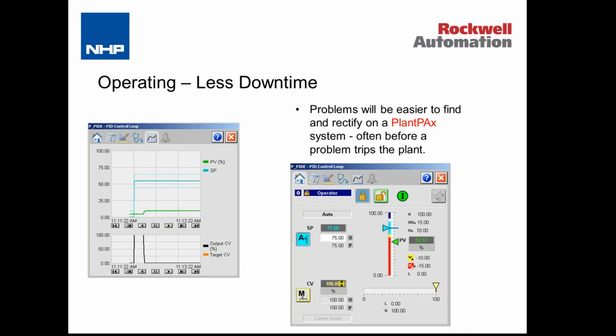Some of the things that you can see here on these faceplates, if we look here at this loop control here, you can see that there's some different coloured bands here showing us where the alarm points are, showing us where the high and low value have been for the process variable over the last period of time. We can see when we're approaching trip points. We can see exactly what's happening on the system, and those features and functions really help us in keeping the plant running and in finding and rectifying problems when they do occur. And I'll show you some of those things when I go to the demo shortly.